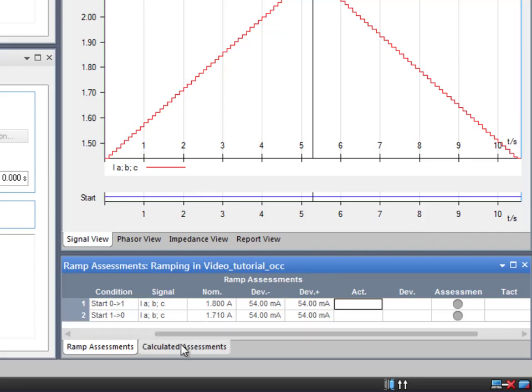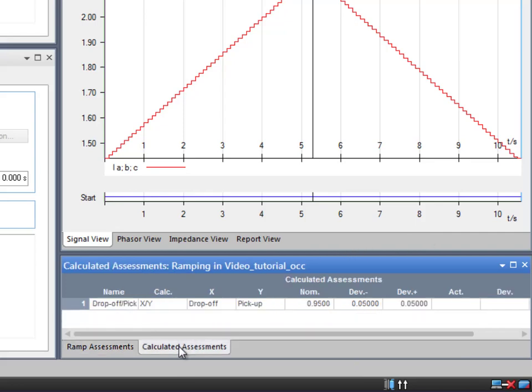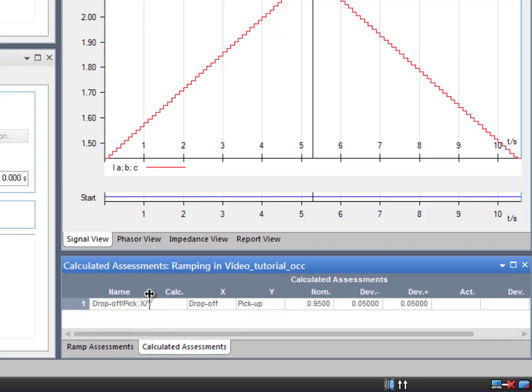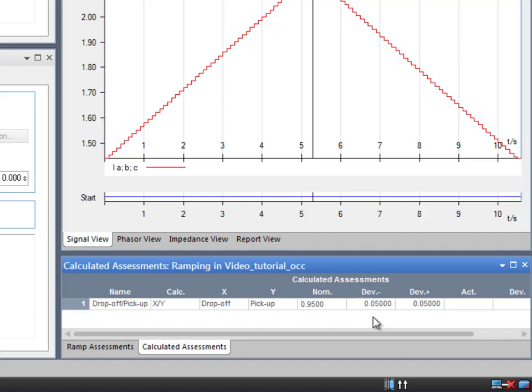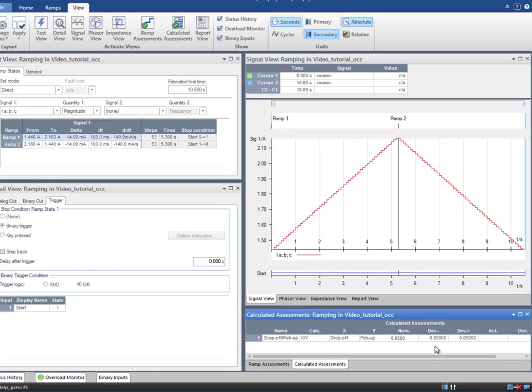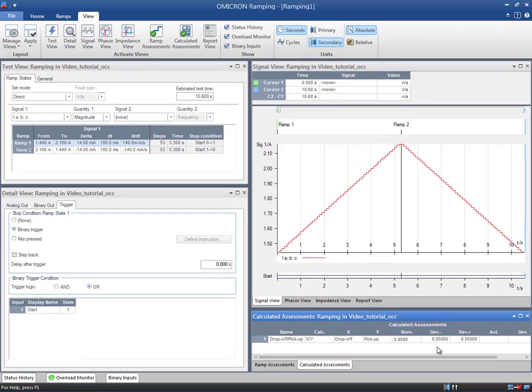In the calculated assessments table, we can define calculations of signal relations, for example, the pick up to drop off ratio. The nominal value will be 0.95 according to the relay's manual. Normally, you do not find any tolerance of this ratio in the manual, so we can keep the default value of 5%. Now, the test is ready to be performed.